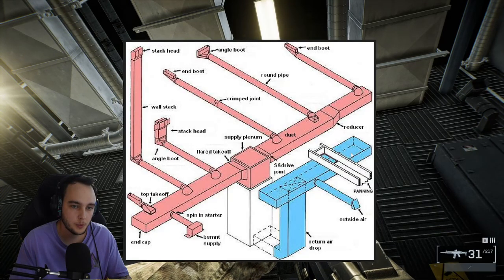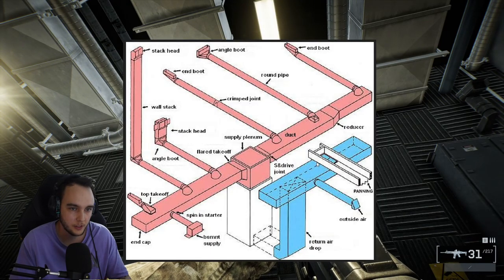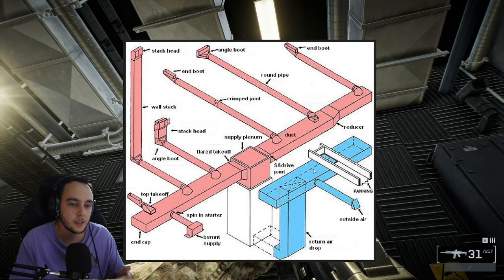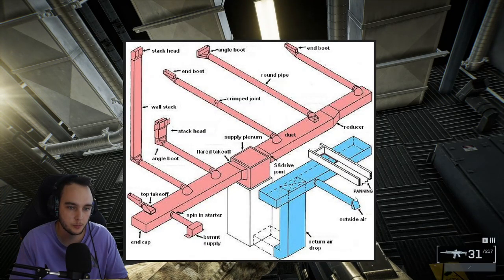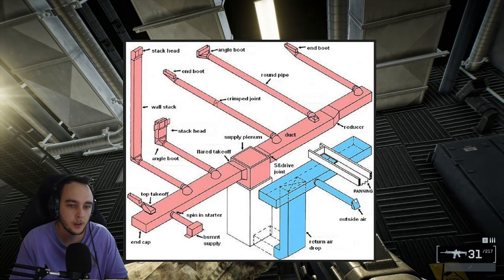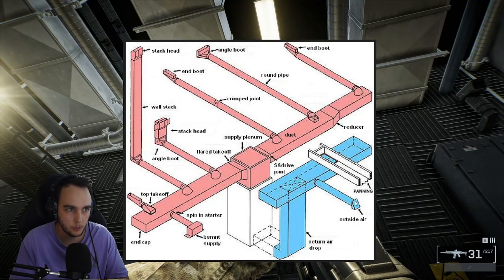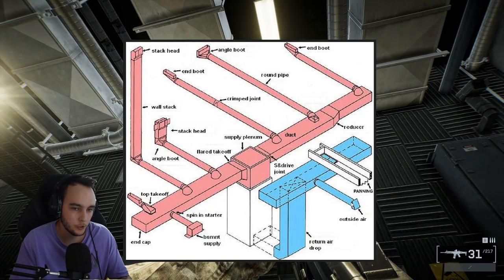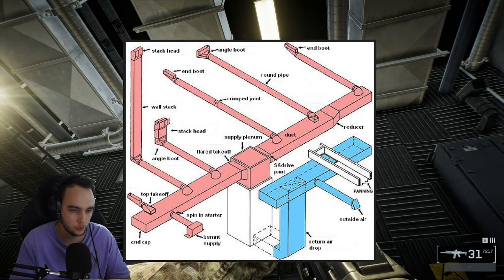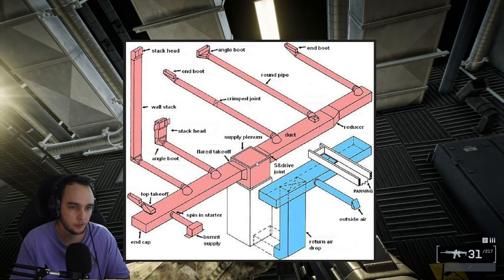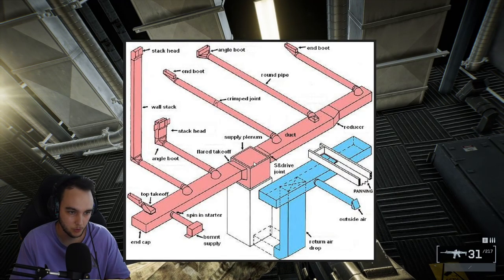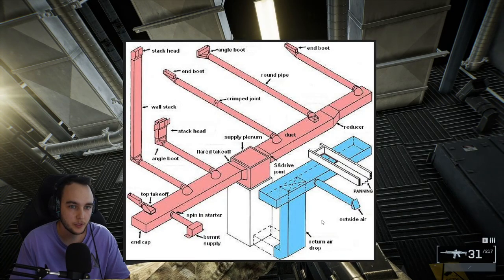Now, typically if you just had the same air going back and forth, supply to return, the oxygen content would deplete. You'd get a headache. If it got too low, you'd basically die. So typically in the return air system, there are little takeoffs for outside air, which basically brings air in from outdoors and adds fresh oxygen, fresh air into the mix, and it becomes mixed air that goes back into the furnace. So it keeps everything fresh and moving, no headaches, no death. And that's typically how the system works.